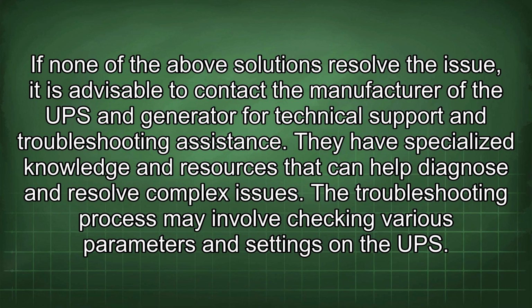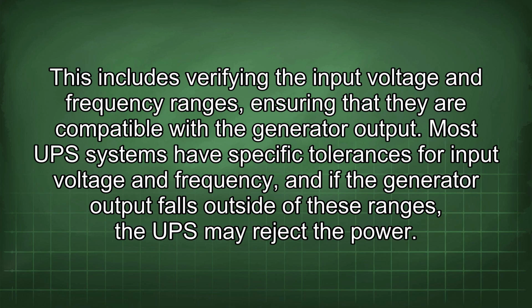If none of the above solutions resolve the issue, it is advisable to contact the manufacturer of the UPS and generator for technical support and troubleshooting assistance. They have specialized knowledge and resources that can help diagnose and resolve complex issues. The troubleshooting process may involve checking various parameters and settings in the UPS. This includes verifying the input voltage and frequency ranges, ensuring that they are compatible with the generator output. Most UPS systems have specific tolerances for input voltage and frequency, and if the generator output falls outside of these ranges, the UPS may reject the power.